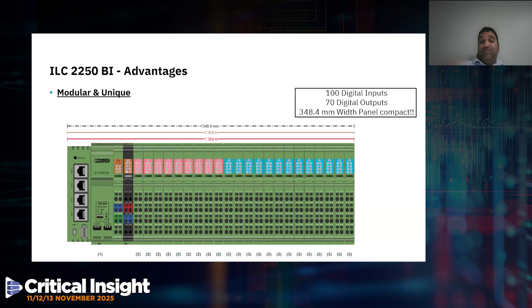We also have a very unique software that allows you to configure just how many points you require, and it will tell you how many modules you need and the power consumption. You can see in this picture that this particular system is going to need at least a power supply of 7 to 8 amps. That's the type of flexibility the software configurator offers, and it's free from Phoenix Contact as well.